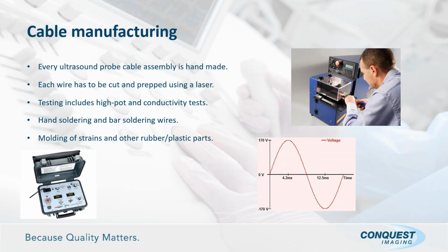Cable manufacturing is another unique thing. Probe cable assemblies are handmade, and I'll talk more about that when I get to the probe assembly, but it's hard to believe in today's world of automation that they're still handmade. The wires have to be cut, prepped, stripped, and most of the time that's done by a laser. Again, lasers are not cheap. They've got to do testing, and cable manufacturers I know of do 100% testing, high pot testing, conductivity testing to make sure that cable's good.